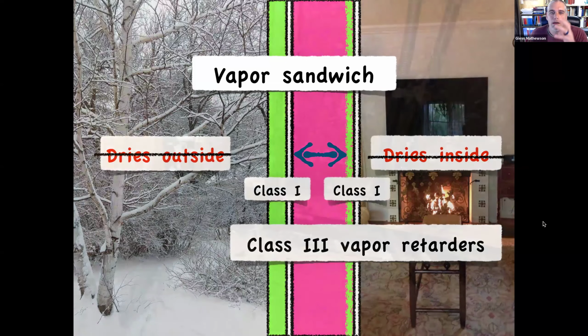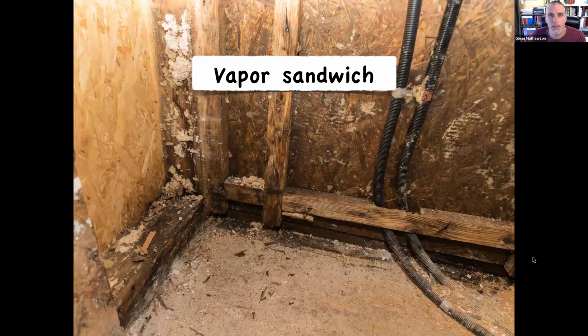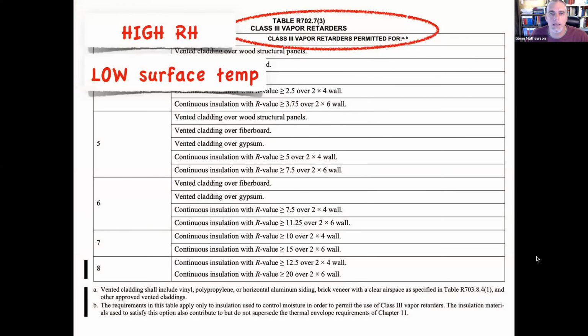We're still getting condensation inside because of air leakage, right? And even with your tightest house meeting energy code, remember that air leakage testing does not measure what's going on inside the envelope. It's only measuring from one side to the other side. So it's up to the building environment to say, what's happening with the air that gets in the assembly? Well, basically recognizing that trying to just block that from happening by stopping the water from getting in there is kind of a losing battle.